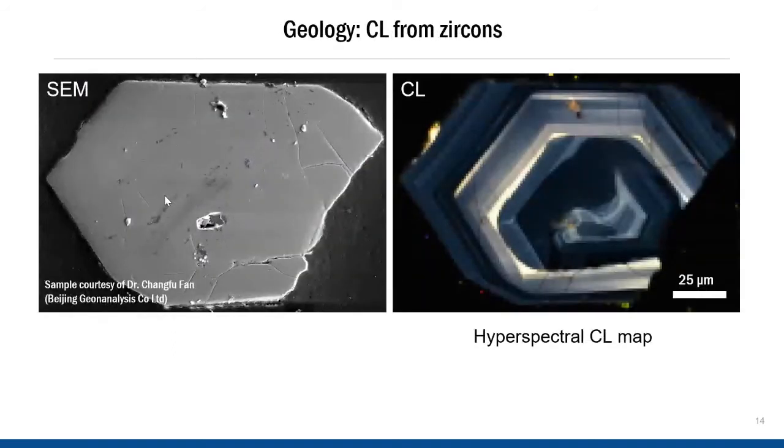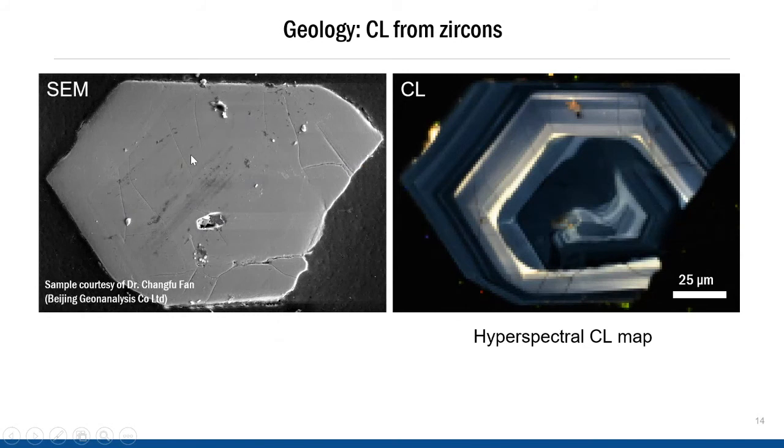This is another example of a zircon now in spectroscopy. It's a spectral map in the range 400 to 650 nanometers, the image that you see on the right here, and this is the SEM image on the left. This CL map was acquired at 10 kV and 375 picoamps current with a pixel dwell time of 200 milliseconds. So the imaging time was tens of minutes. For other materials like phosphors or direct band gap semiconductors, you need less current to get a high quality image. And then for some materials, you may need much more.